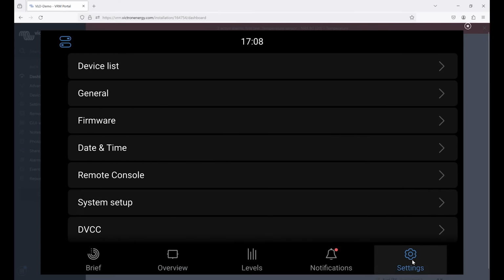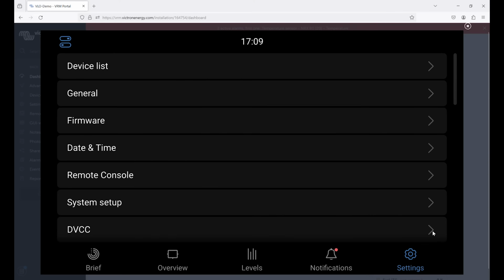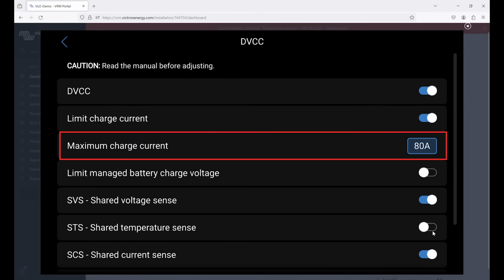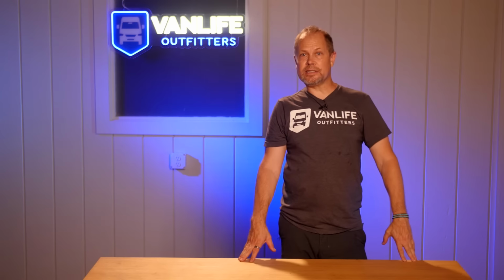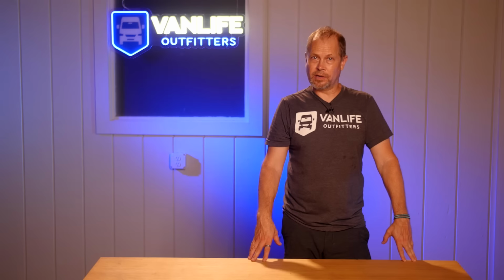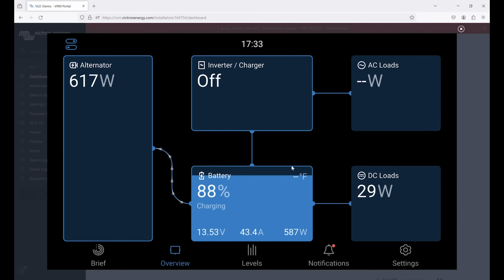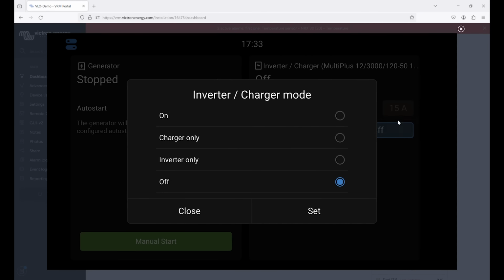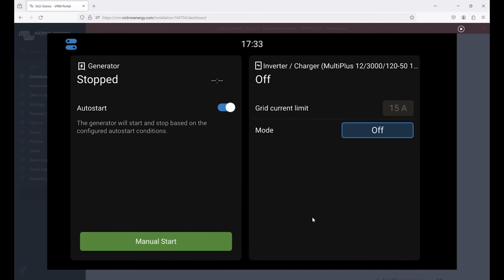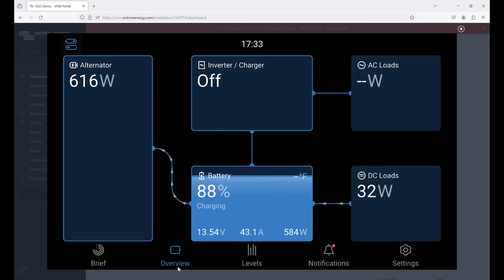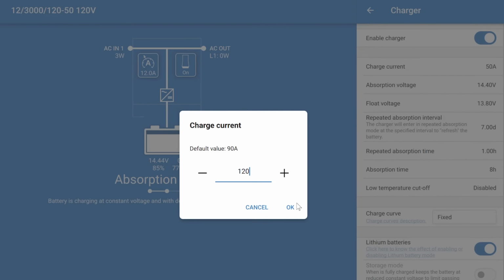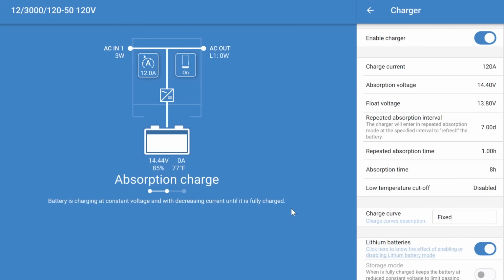Now I'm going to change that system-wide maximum current to 80 amps from 100 in the DVCC settings. This will demonstrate how the system will prioritize free power from the DC to DC charger over what is typically metered power from our shore power coming in from the Multi-Plus. So I'll turn on the Multi-Plus inverter charger, which is connected to shore power so it can also provide a charge. It's configured internally for the maximum charge current of 120 amps, which is the factory default.